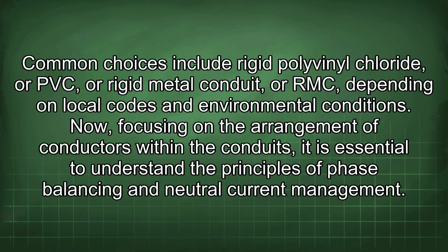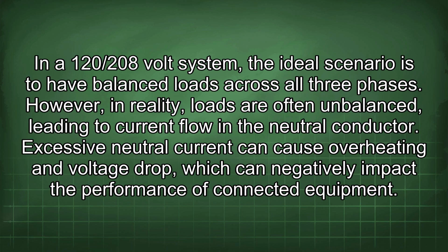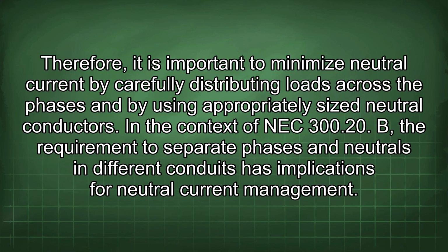environmental conditions. Now, focusing on the arrangement of conductors within the conduits, it is essential to understand the principles of phase balancing and neutral current management. In a 120/208 volt system, the ideal scenario is to have balanced loads across all three phases. However, in reality, loads are often unbalanced, leading to current flow in the neutral conductor. Excessive neutral current can cause overheating and voltage drop, which can negatively impact the performance of connected equipment.